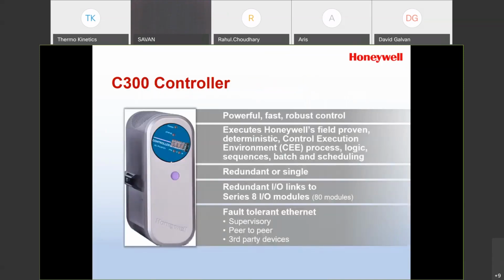So it's a complete DCS and SCADA, with the powerful C300 controller that's been around forever, since the late 80s, early 90s. It's a supervisory system, peer-to-peer, with direct connectivity to your stations. That's the difference between a full SCADA system and a DCS. With a SCADA system, your point repository is in the server. So if you lose your SCADA server for any reason, you lose view. You don't lose control, because your control is being done at the PLC level, but your view is gone. With a DCS, this controller is connected directly to the station, so you never lose view, never lose control. And you can also have SCADA devices connected to this system as well. So it's a 2-in-1.